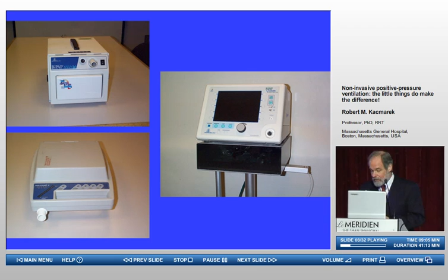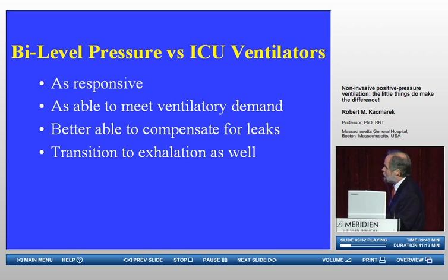First, let me make a couple comments about this group of mechanical ventilators. At least in the literature that's been published comparing operational capabilities, gas delivery capabilities of these units, they clearly are at least as responsive as ICU ventilators. They're capable of meeting patients' ventilatory demands. Most have peak inspiratory flow capabilities of up to 200 liters per minute, at least as good as the ICU ventilator. Most transition to exhalation quite well and are able to compensate for leaks. And this is probably the key advantage of this group of mechanical ventilators. All of them are designed to compensate for the leaks that do occur anytime we provide non-invasive ventilation.